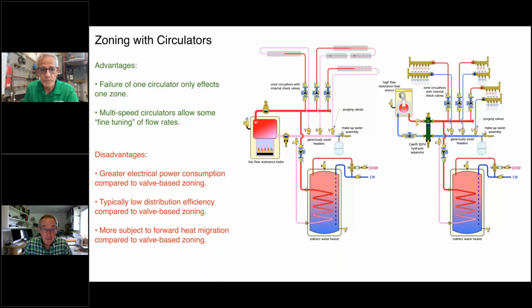Yeah, and that's getting critically important because we're seeing more and more ECM circulators come in. And keep in mind that some of the OEM circulators that are coming into modulating condensing boilers, and especially heat pumps, air to water heat pumps, those are ECM circulators. We don't want to pump magnetite into a brand new heat pump. We're going to foul up the heat exchanger and potentially have some problems with those internal circulators.